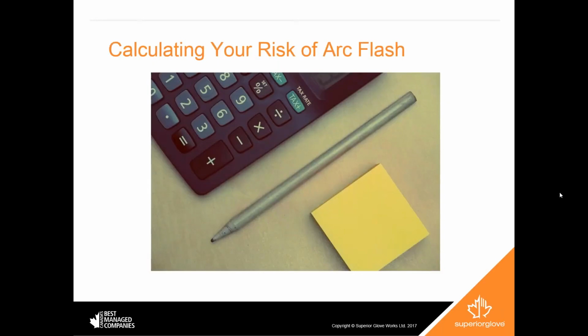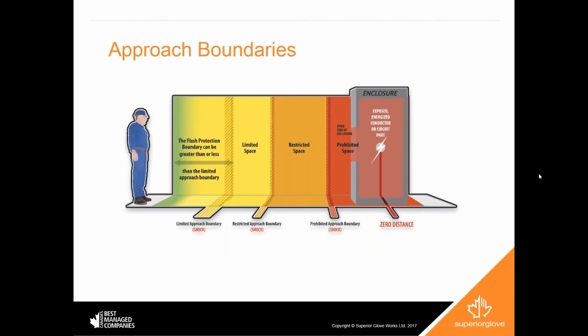All right, and so from here we should talk a little bit about calculating your risk of arc flash. Different areas where you are from a piece of machinery, you're going to have a different risk factor. So in some cases you do have to work on energized equipment. So the National Fire Protection Association developed specific approach boundaries designed to protect employees. In the next slide, we will look at those different approach boundaries.